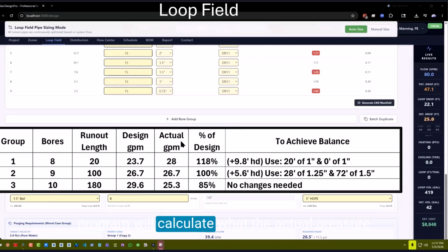But the program will calculate what the actual pressure drop is based on how the flow will naturally balance. In this extreme case, the closest loop is going to be 18% over design, and the furthest group is going to be 15% under design. Now, you can debate whether or not that is a problem. Personally, I don't think it is. Keeping in mind you're sending the same temperature water out to all these groups. So the one that's got 18% more flow will simply have an 18% lower temperature change.